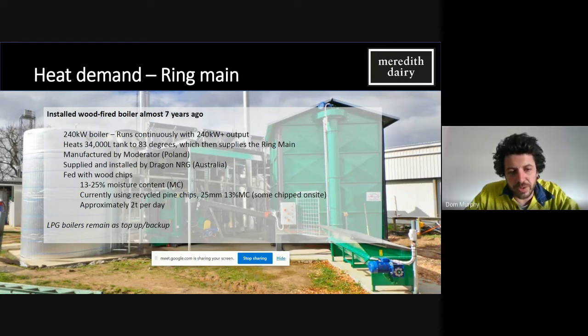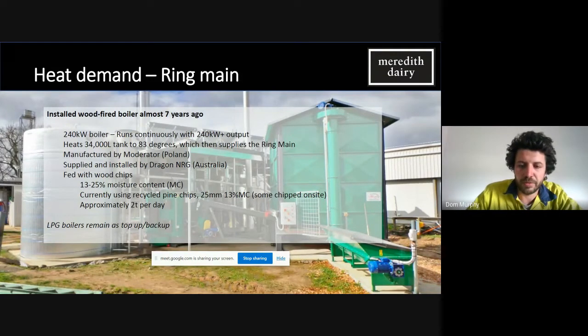We have LPG boilers that remain. They were installed around the same time as the wood boiler, and they remain there as a backup in case we have to do maintenance, or to top us up when our demand exceeds what the boiler can provide.